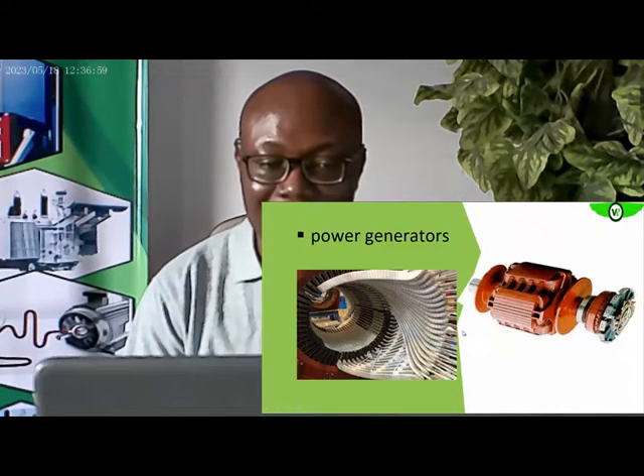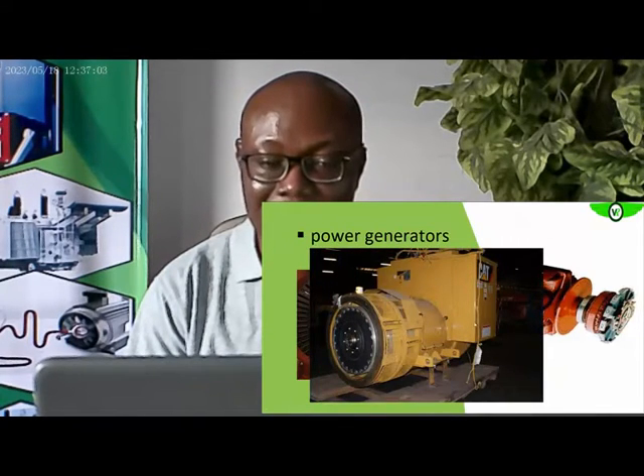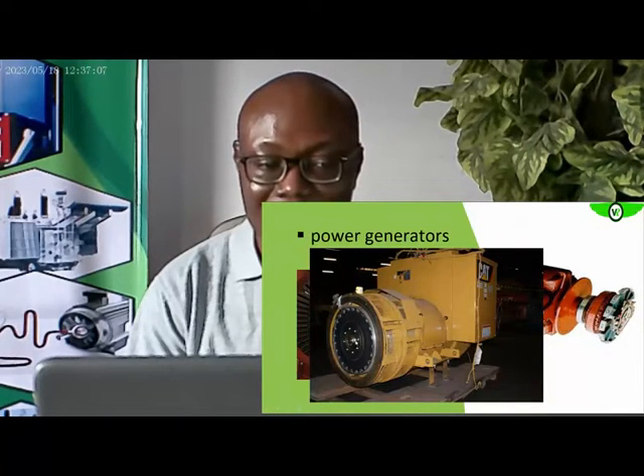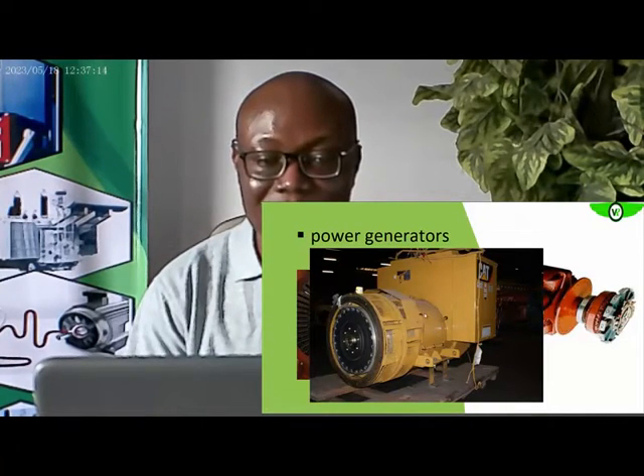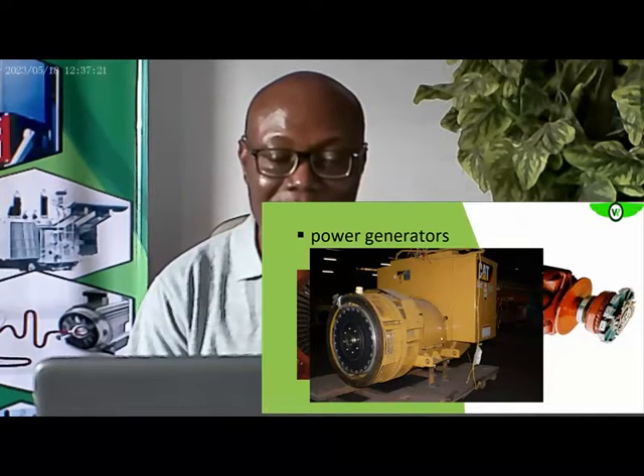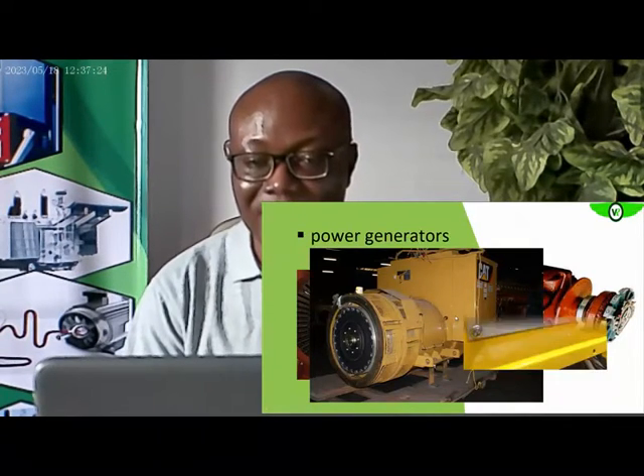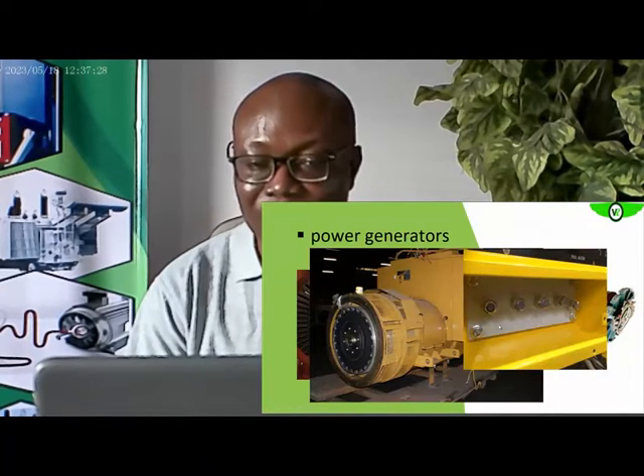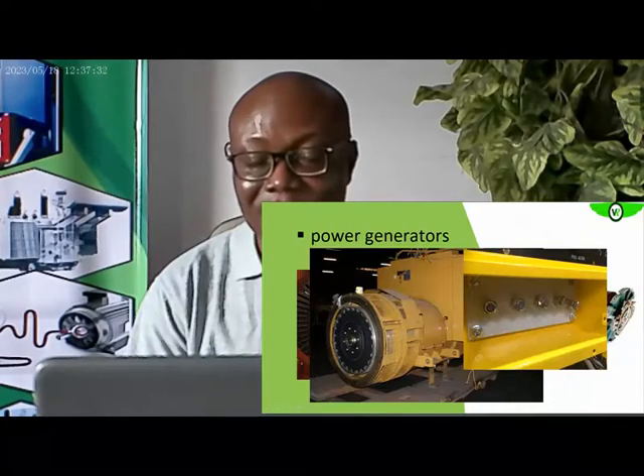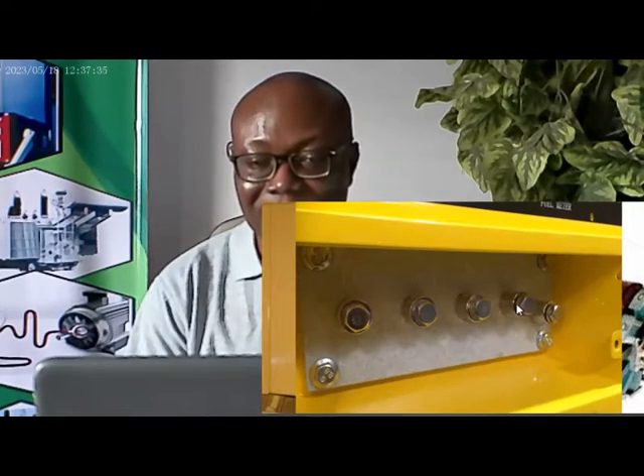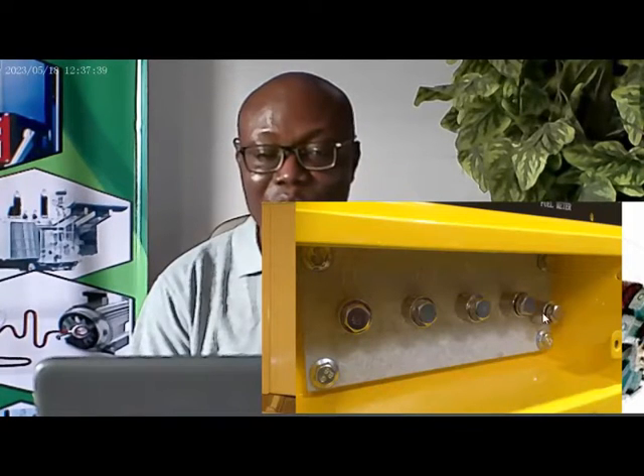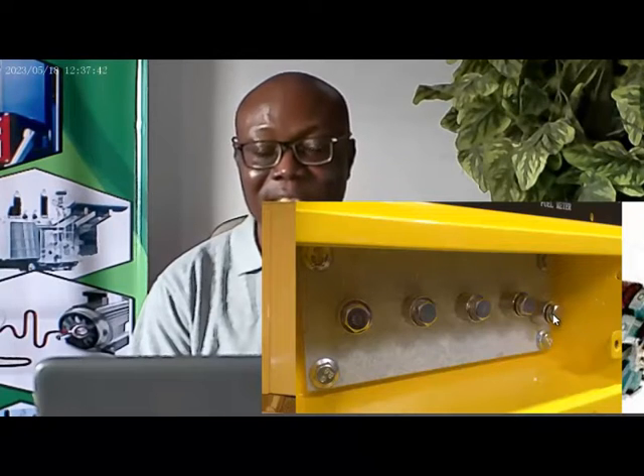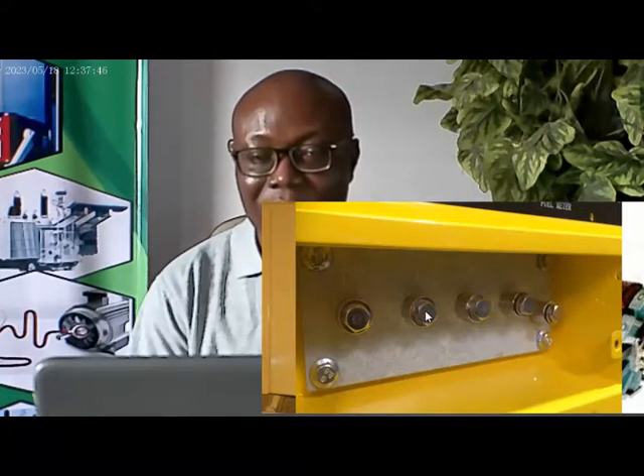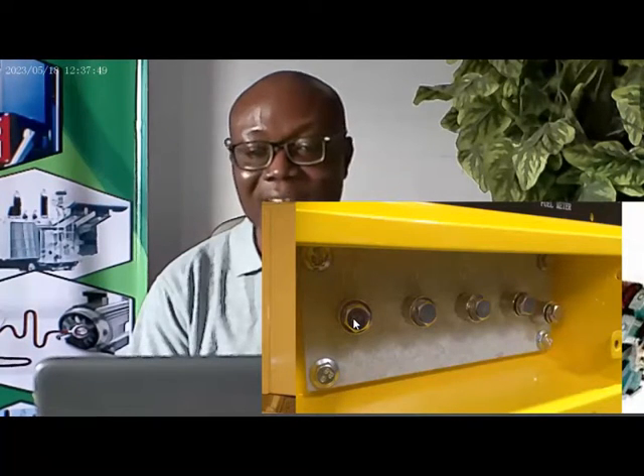So this is what you actually see. This is a coupled alternator, that is, this rotor has been coupled into this stator of the generator. That is what we have here. What will be exposed to you is the terminal block, not the winding. When you open the terminal cover, what you have is something like this. This is the U phase, V phase, W phase, and this is the neutral, which means the star point, and this is earth. From what we saw inside, since it is star connected, the 3 windings have been connected to one another, so you can only take insulation between the winding and ground.